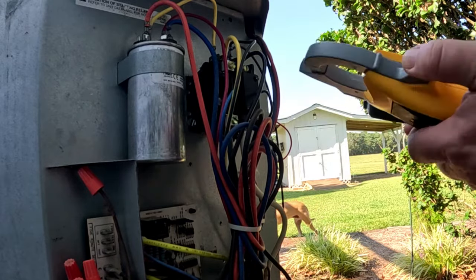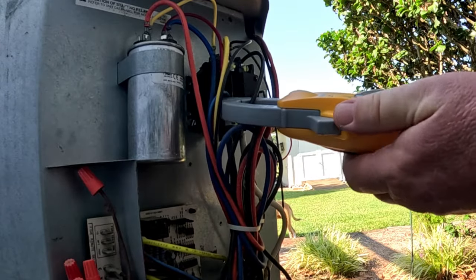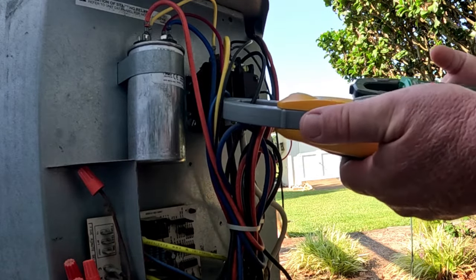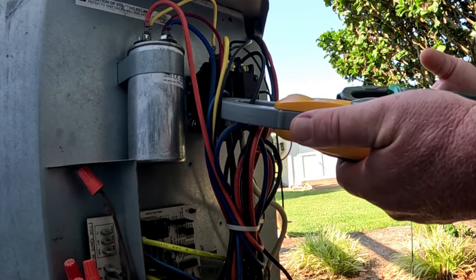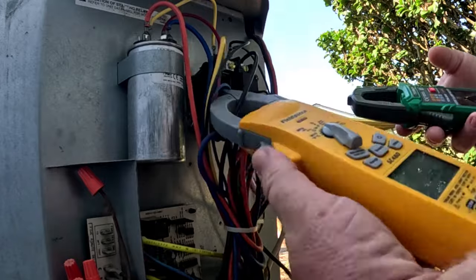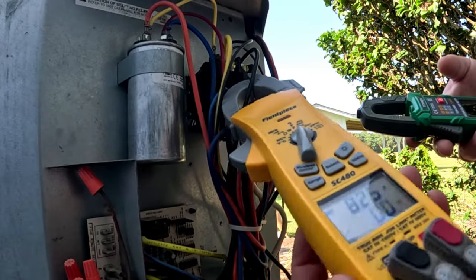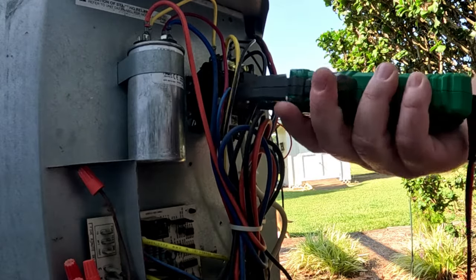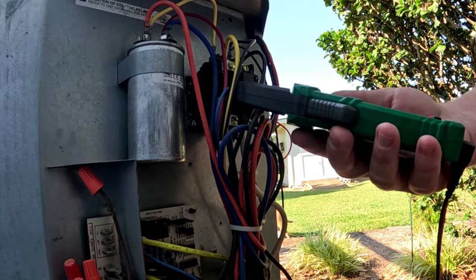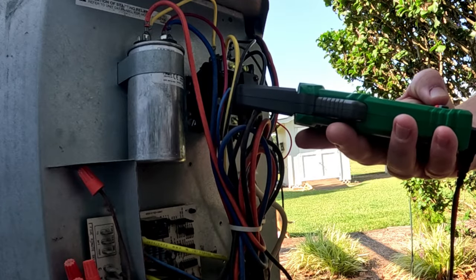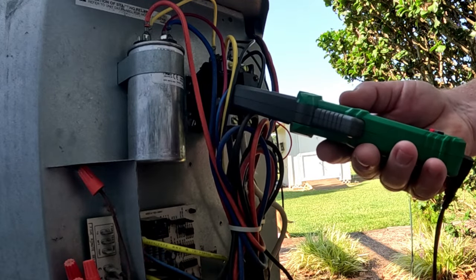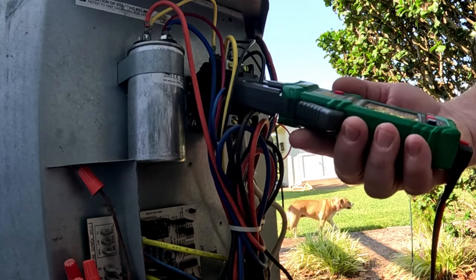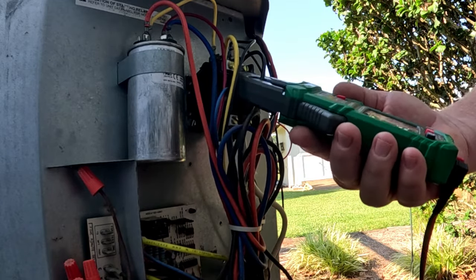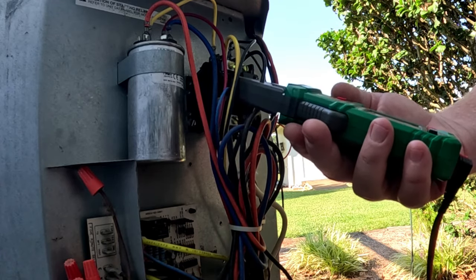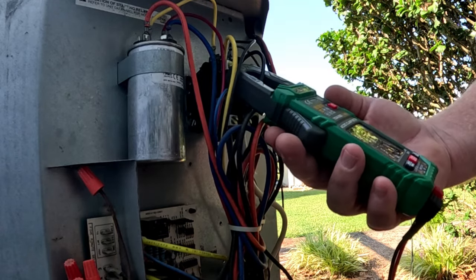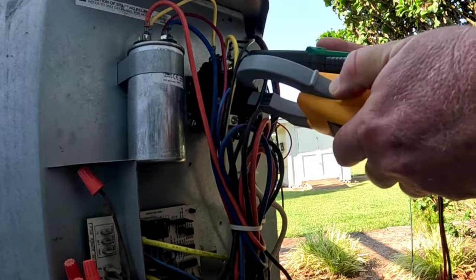So let's see what our operating amps are. So we're getting 8.4 operating amps on the FieldPiece. Right there, 8.2. Let's see what this gives us. And I may need to take it out of the inrush function. We'll just turn it off, turn it back on. And it's giving me 8.4. So 8.4.